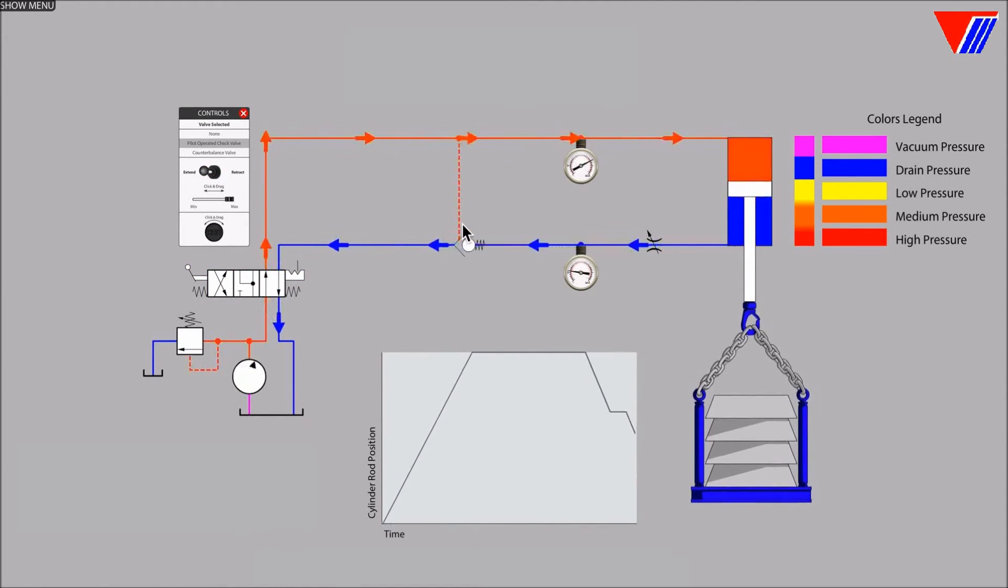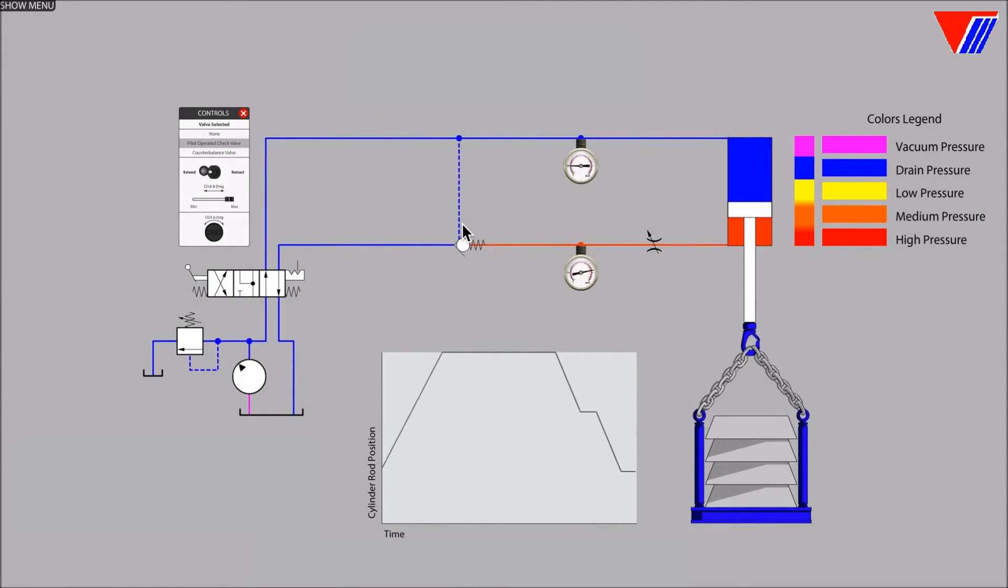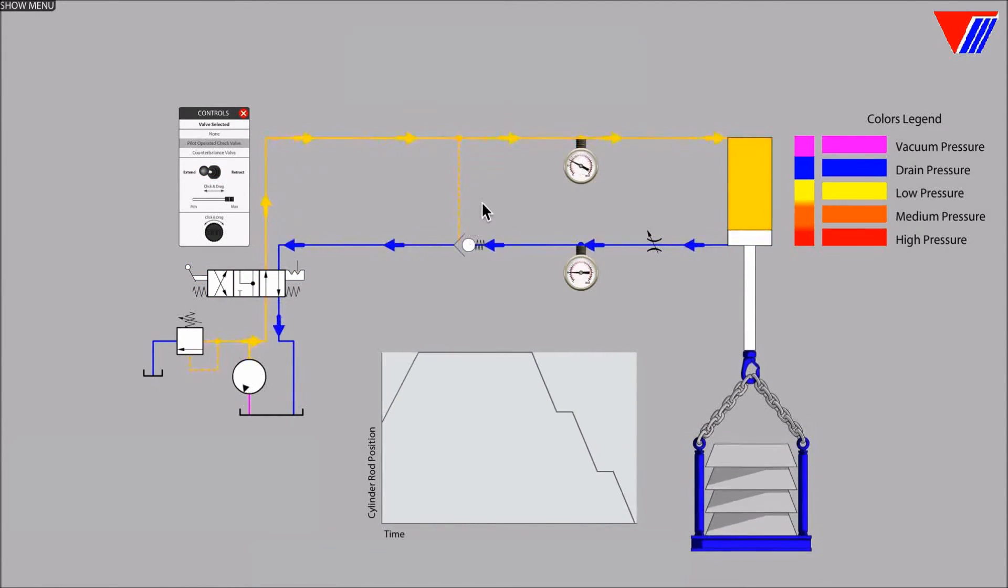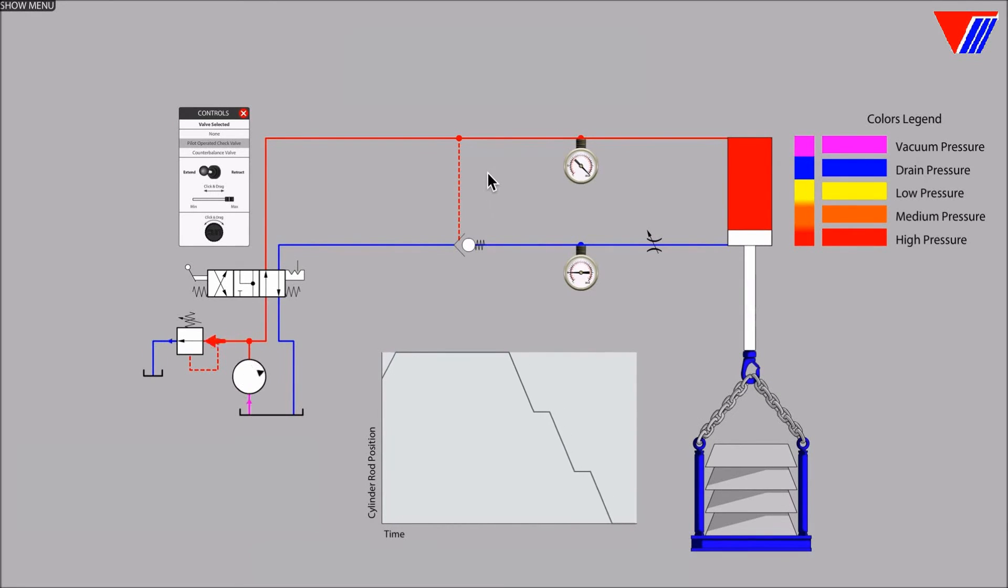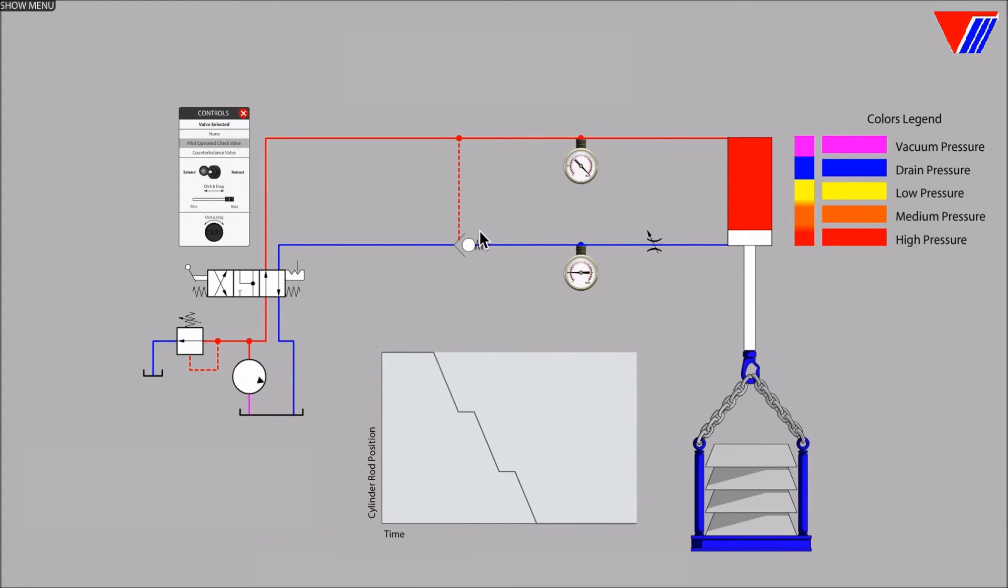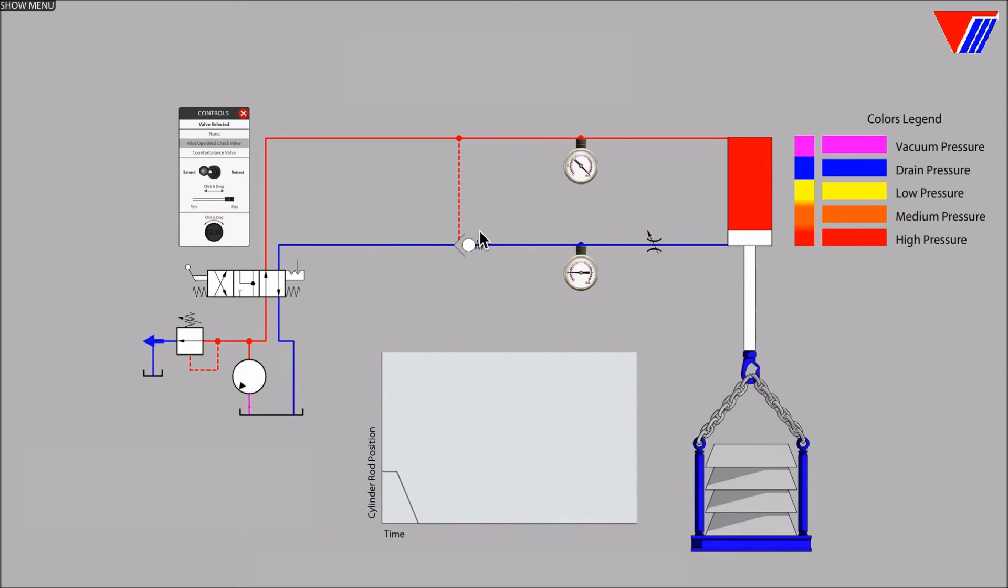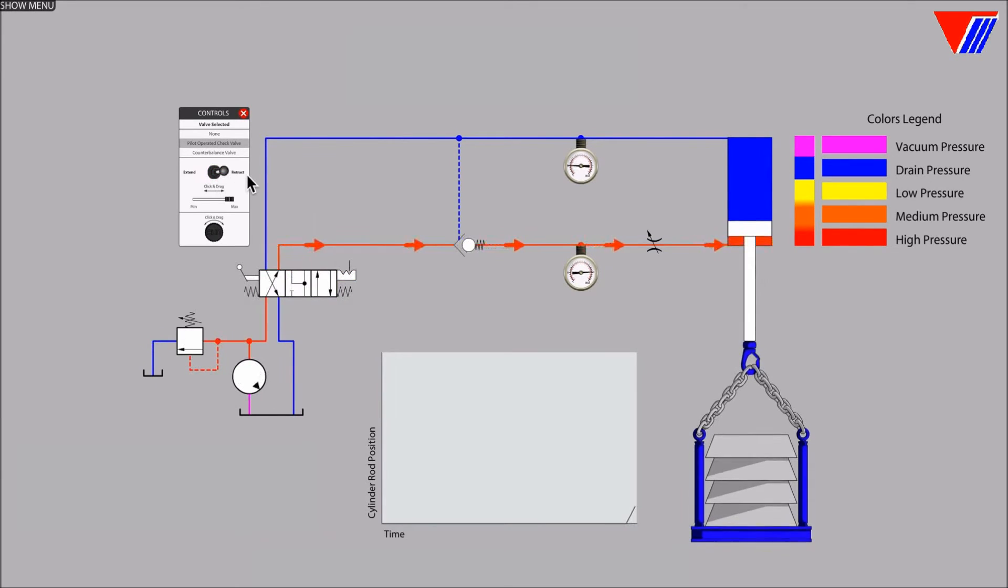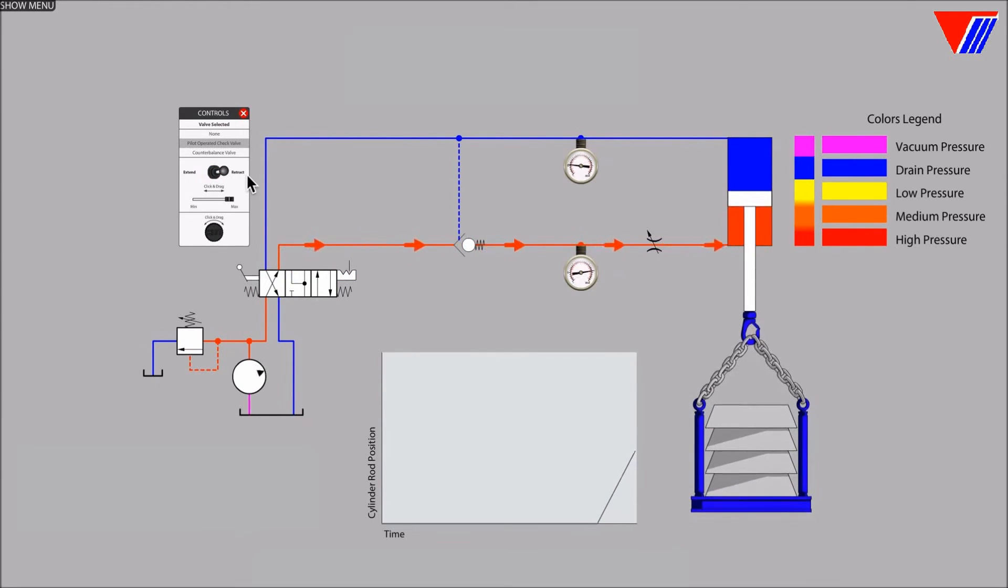Whenever the check valve halts cylinder motion, pressure builds in the upper line once again, piloting the check valve to the open position. Cylinder motion resumes and accelerates and the runaway motion control problem repeats itself.